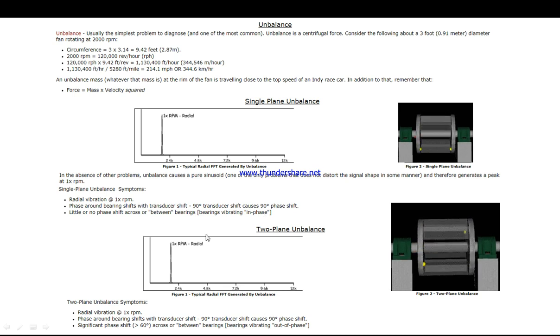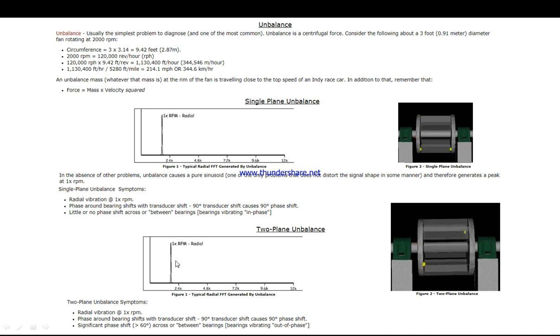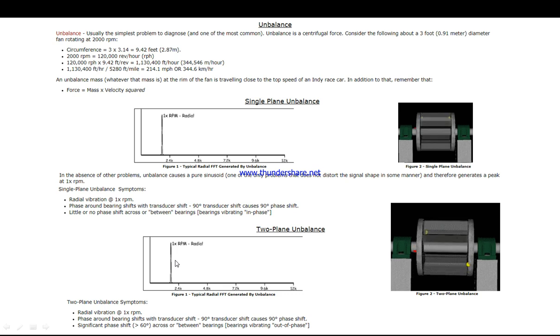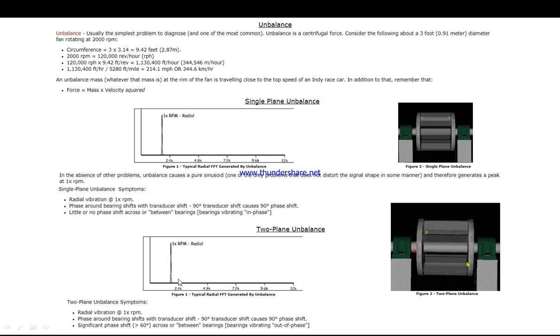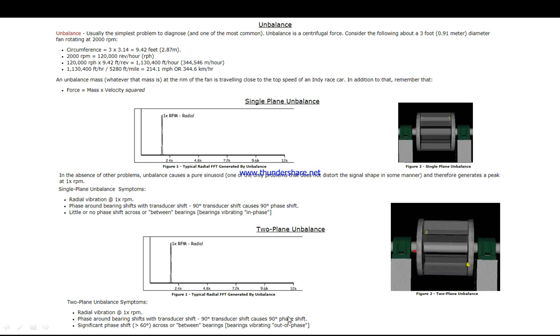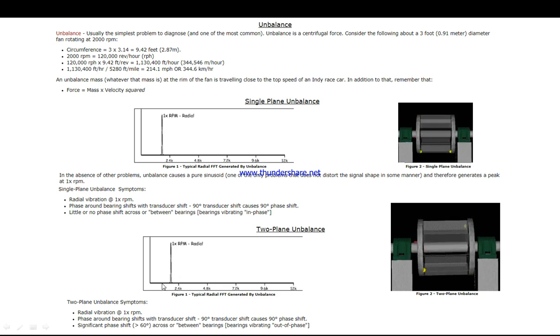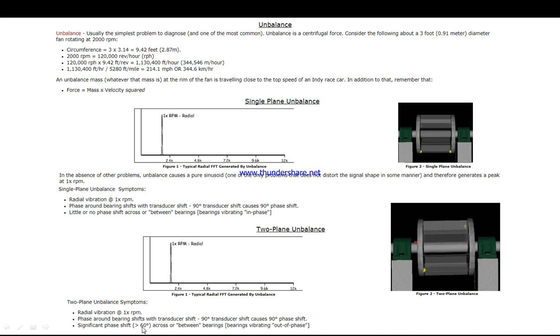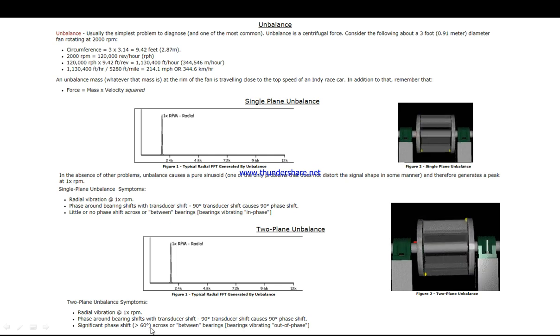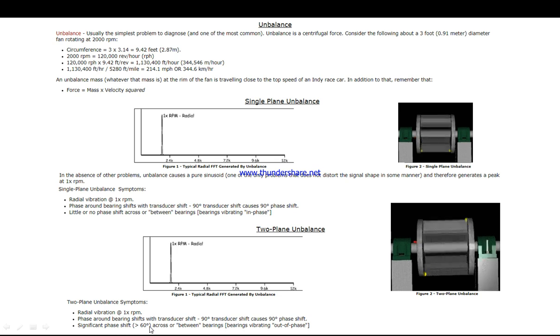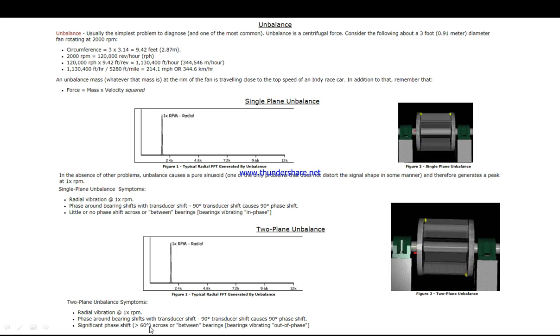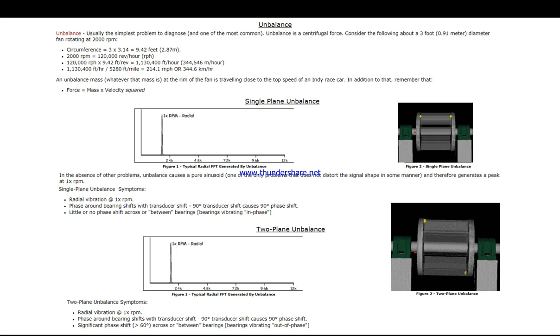For two plane unbalance: same 1x RPM, 90 degrees phase around with transducer, and significant phase shift between one bearing and the successive bearing for more than 60 degrees. But you have to go back to the phase triggering strobe light.